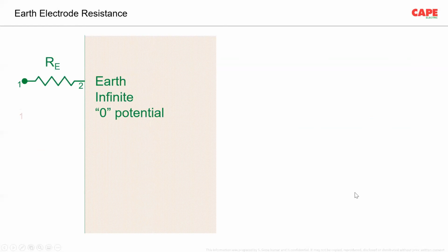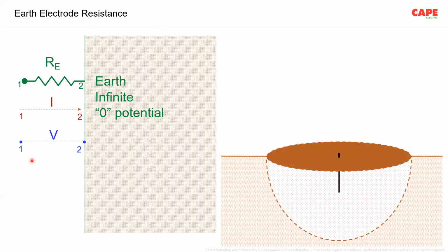Yeah, you have the resistance R, and whenever there is a current flow through this particular resistance, you know very well there is a voltage drop in that resistor. Now, if we put it in an actual situation, you can see earth electrode number 1, the point at which you are connecting is point number 1. Then you have the earth electrode in soil. Then you have, like a sphere, an area in soil, and your infinite earth is point number 2, which is far away from the earth electrode. Nobody knows how far. We can only make some calculations and take some approximations.